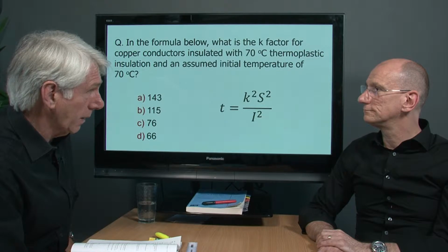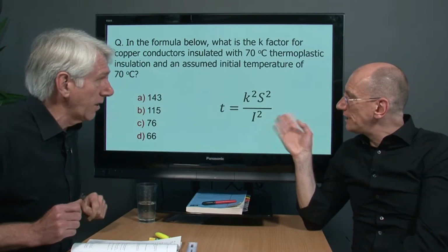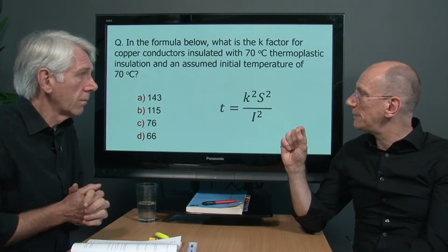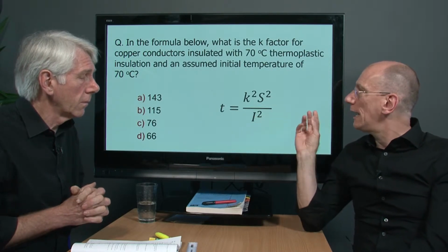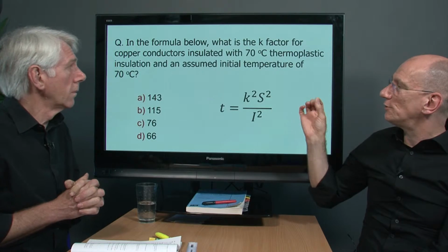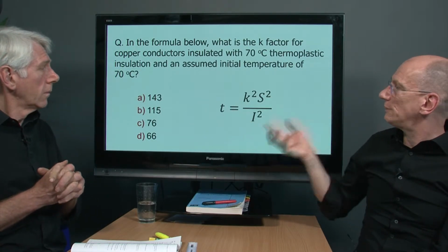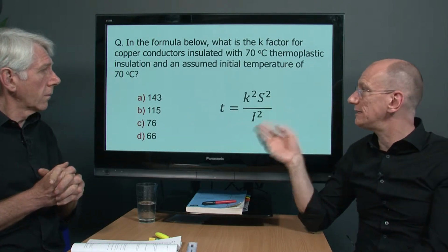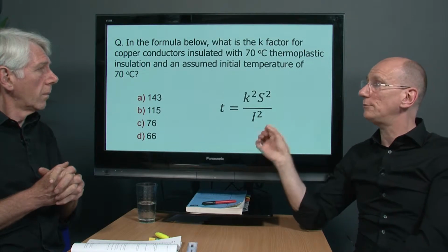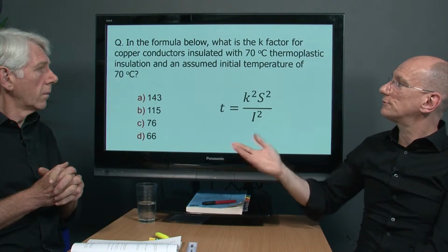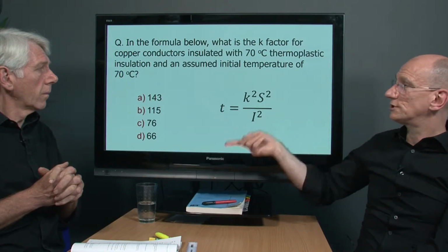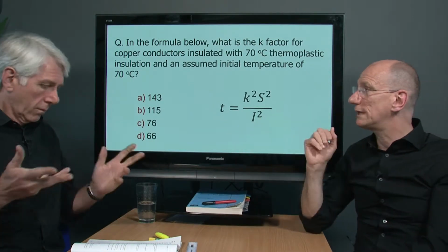So, do we go straight back to it, Gary? Do we go to page 196? This particular one is a variant on the adiabatic. Most will be familiar with the S is equal to the square root of, etc., etc. But the bit that is not unique but synonymous across the board is K values apply irrespectively. This one is dealing with time, on how long the conductor can cope without being burnt out, and the other one deals with the cross-sectional area. But it doesn't matter. Just go to the table that you went to before.